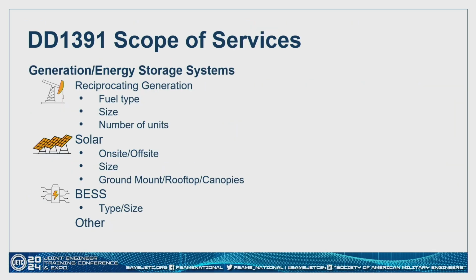Scope of services: for a microgrid, it will tell you what size generation you're going to have, and very often the fuel type—natural gas, diesel, solar—whether the solar is on-site or off-site, and how much solar you're putting in. These are things you cannot change on the project; that's what it's been defined as. It will also tell you the BESS—battery energy storage system—size and number. This document is the Bible. It tells you your project parameters, and you need to get this right.